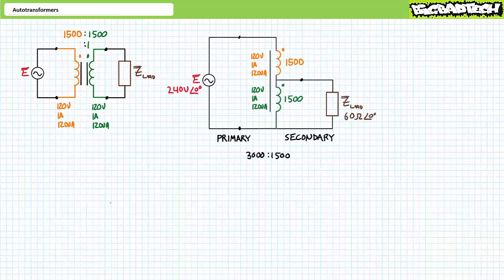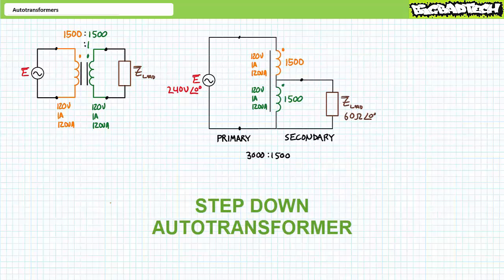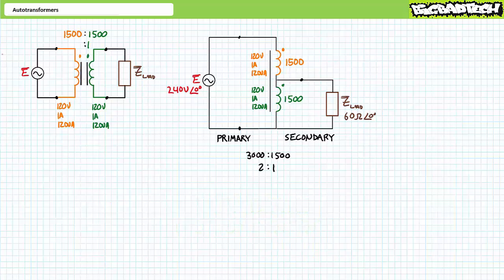If isolation isn't a necessity, consider the following modification. Configured as a step-down auto transformer, one would connect the previously isolated two windings in a series aiding fashion, allowing a total of 120 plus 120 or 240 volts to be applied across a single winding. Output is then taken across half the larger winding. The primary input winding becomes 1500 plus 1500 or 3000 turns, and the secondary output winding has 1500 turns, even though they're part of the same winding. We've in effect created a two-to-one step-down auto transformer, where 240 volt input results in 120 volt output.